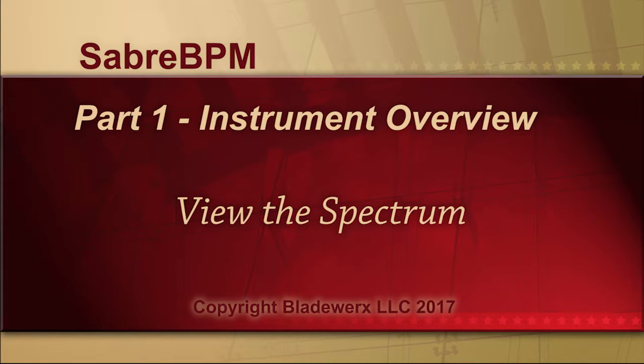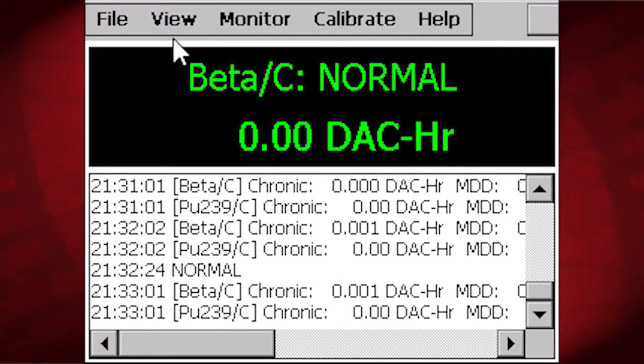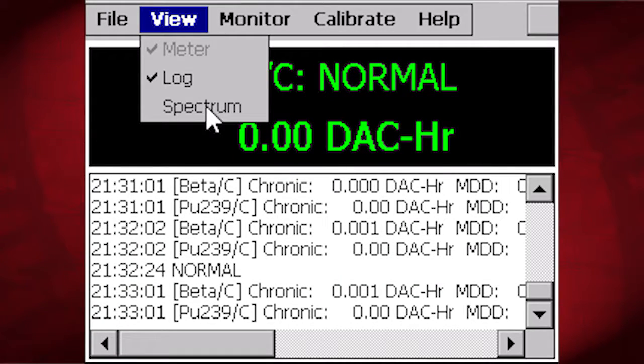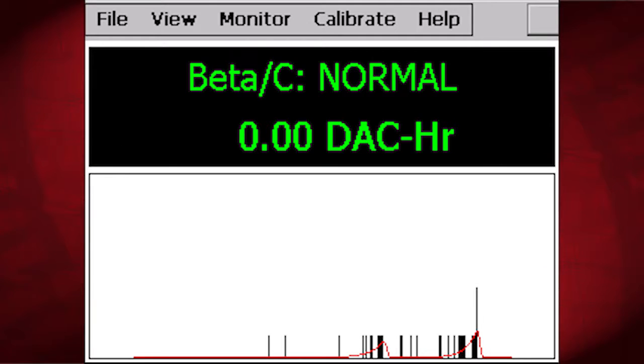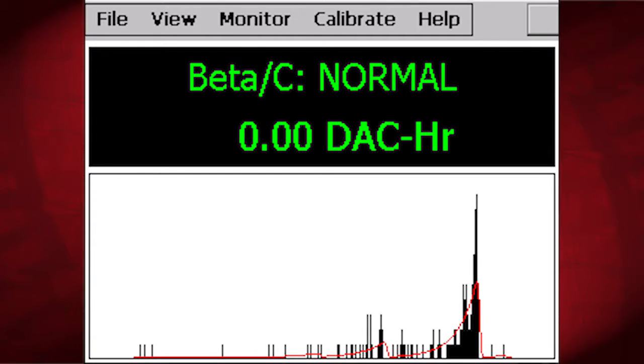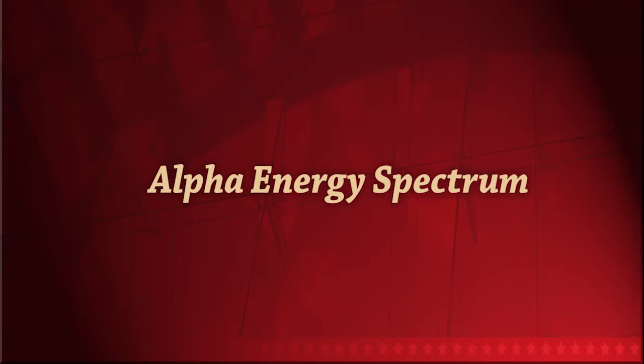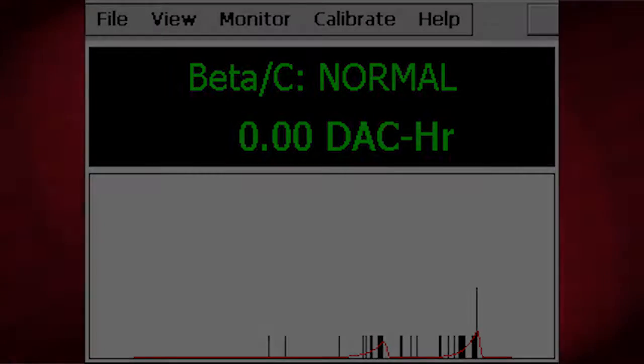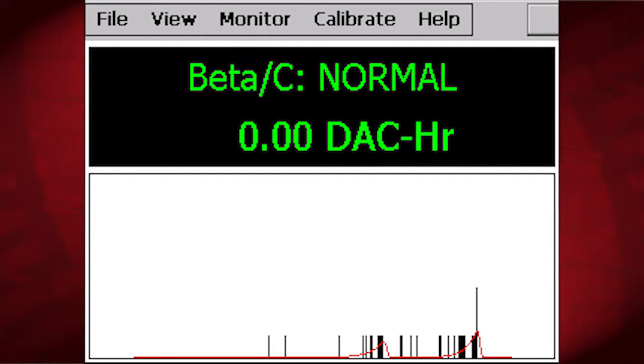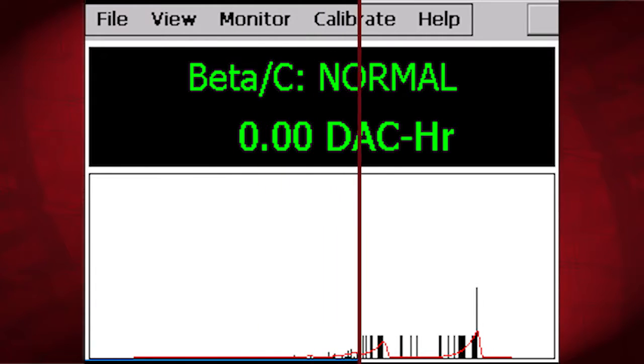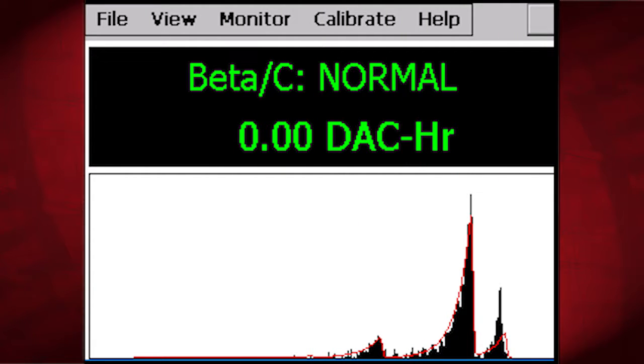Okay, now we have one last step before leaving the instrument to continue its air sampling. In the menu, click View, then Spectrum. In place of the historical log is a bar graph. The x-axis is alpha energy and the y-axis is the number of alphas having that energy. So as more and more particles decay at the same energies, the taller those energy columns, or channels, will become. This is what we call an alpha energy spectrum. Right now, it is very sparsely populated, but as the BPM accumulates more data, a spectrum with 3 peaks should form from the naturally occurring radon progenies in the ambient air.